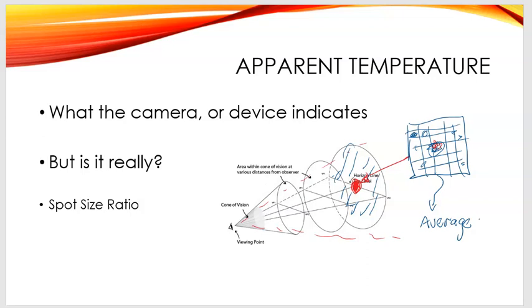And what I'm saying here, think of that as the array that is being used. The camera's picking the light up, and the little pixels are being pulled in, and the temperature off that one little part is what's recorded. Which means if you can bring your camera up close enough, the camera will pick up the entire object, and so you do have the full temperature. So you've got to be careful with that.